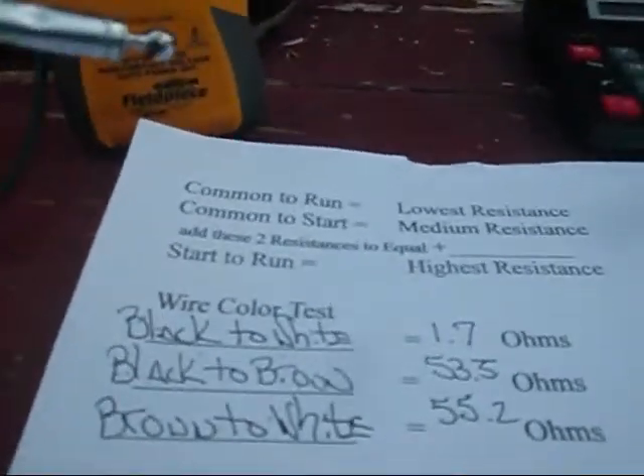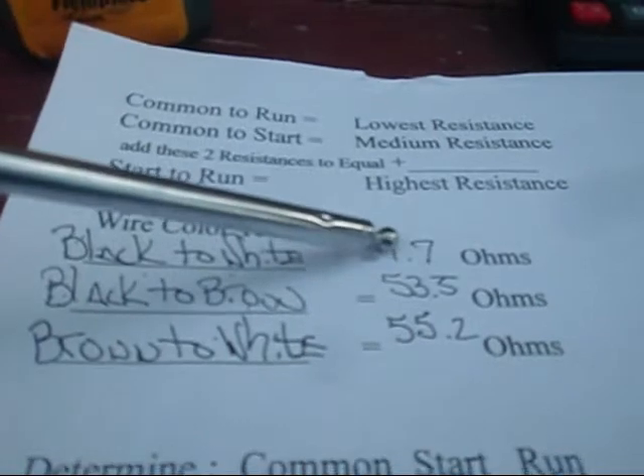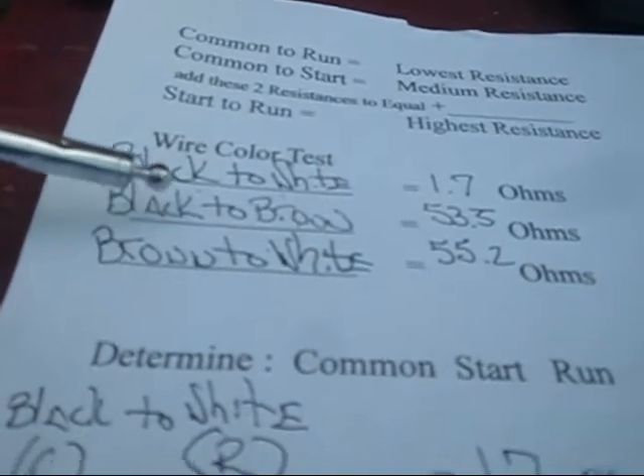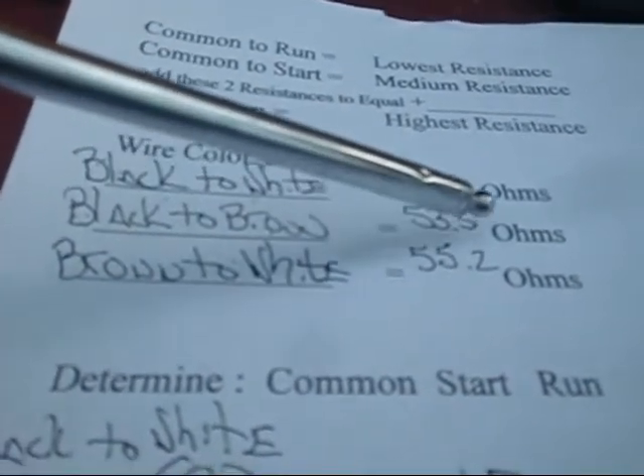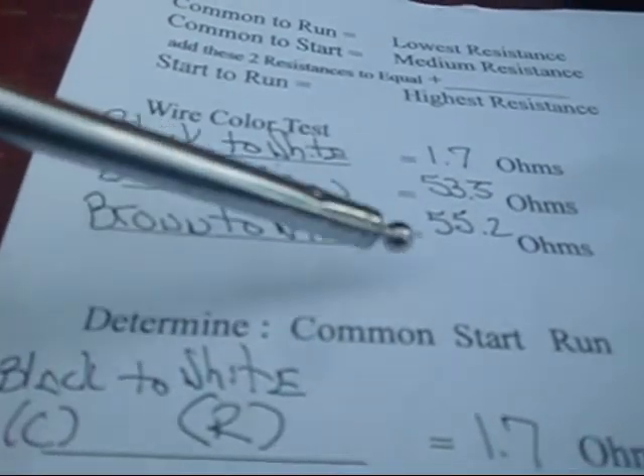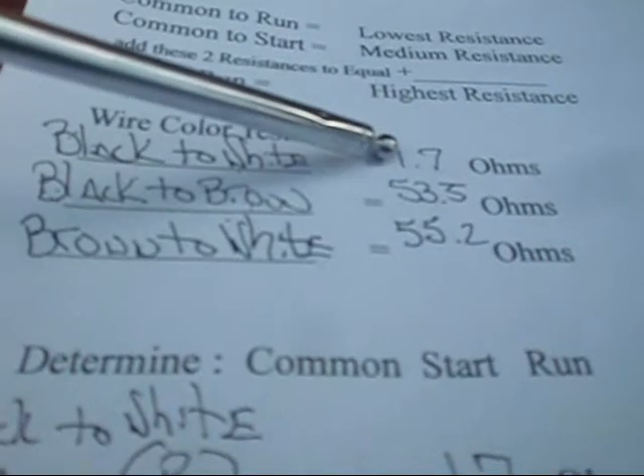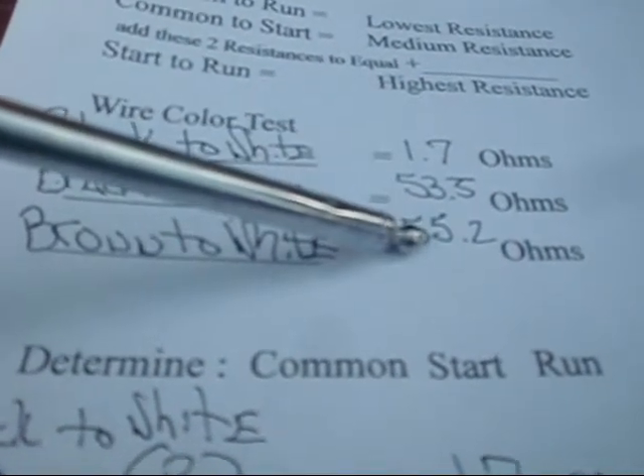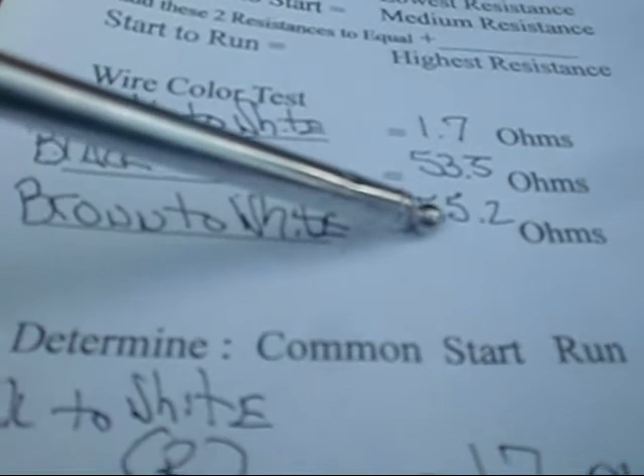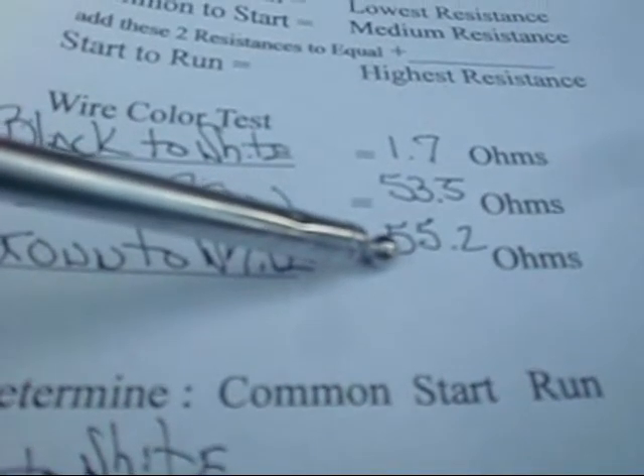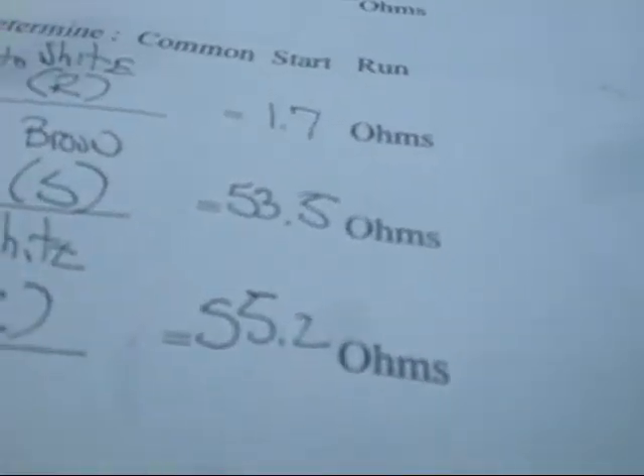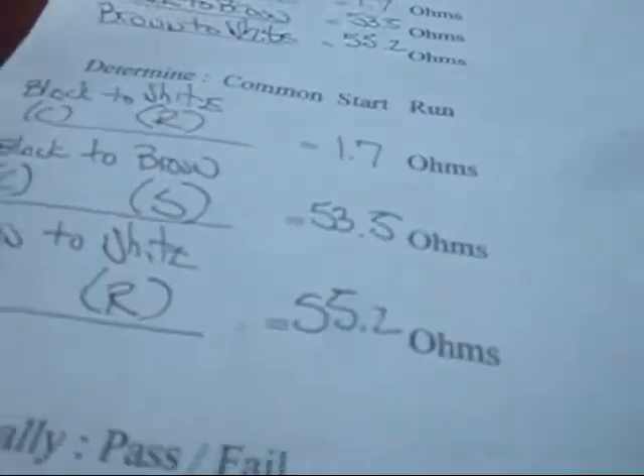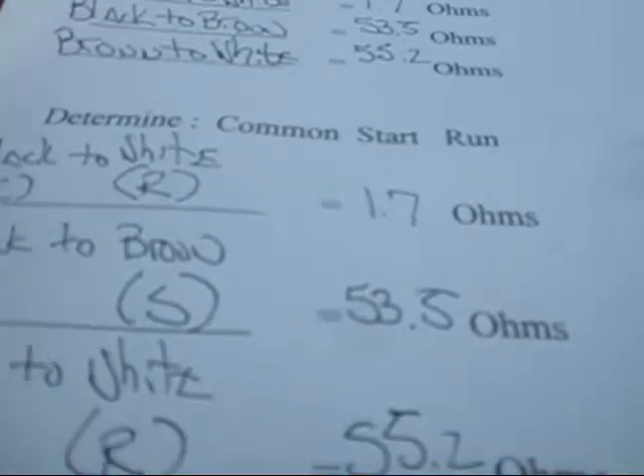We started out and we ohmed out our black to our white wire, we came up with 1.7 ohms. We ohmed out our black to our brown wire which we came up with 53.5 ohms. We ohmed out our brown to our white wire which was 55.2. We added 1.7 plus 53.5 and we came up with exactly 55.2. Guys, it's not probably going to be always exactly right. I mean if it's way out, we know we got a bad problem.